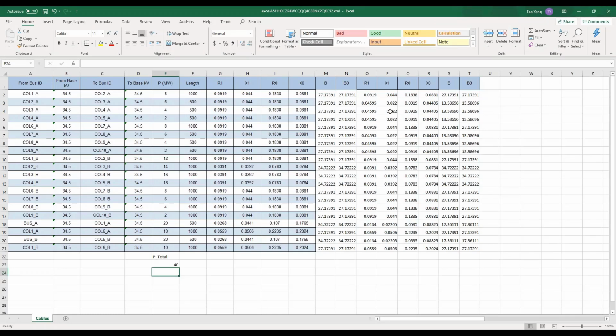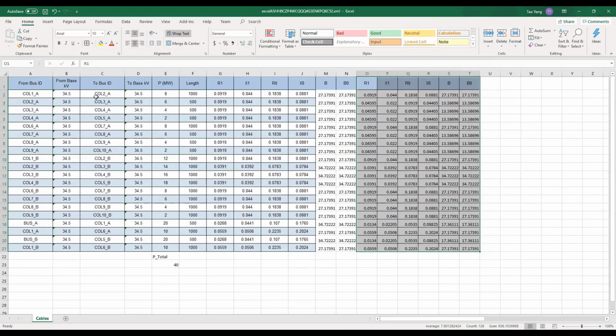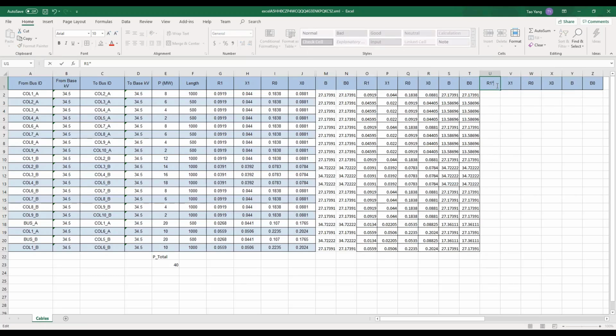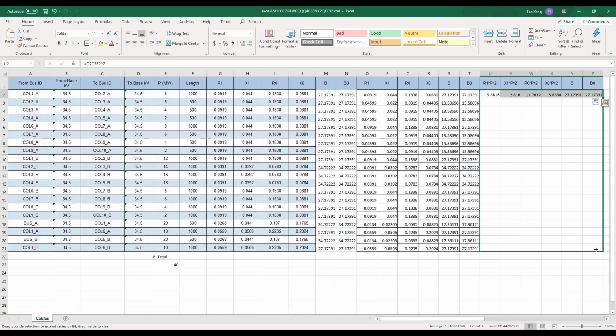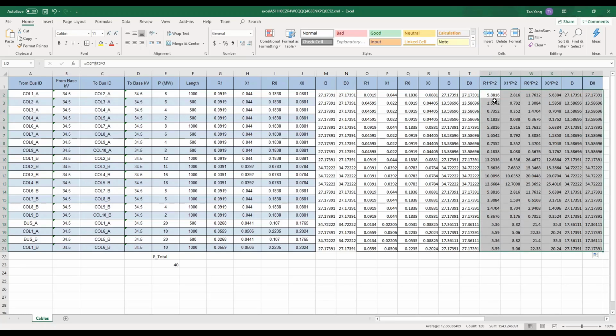So now we need to plug in the formula or the equation to find out what exactly my collector system equivalent looks like. Step 1 is that we need to make sure I got it right. This is my R1 times P squared, X1, R0, X0. I don't have to do that for B because line charging is just simply add up, right? So my resistance would be R1 is equal to the real R1 times P squared. Now I need to keep locking this E2 column to avoid shifting. This B is equal to this B directly, right? I need to copy this equation as well. Now I copy all the equation down. Now I have my product of P squared times each item.